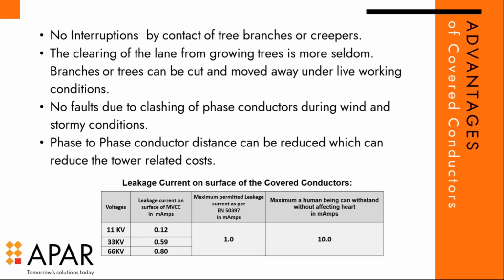But since government approvals are not yet there, we are keeping the same phase-to-phase distance as used for 11 kV or 33 kV. However, when using covered conductors, you can reduce both the phase-to-phase distance and the phase-to-earth distance.